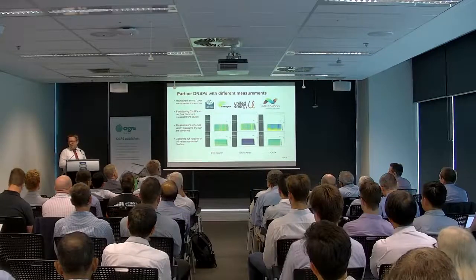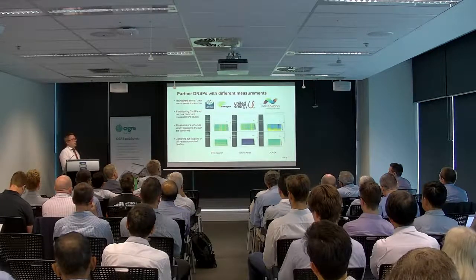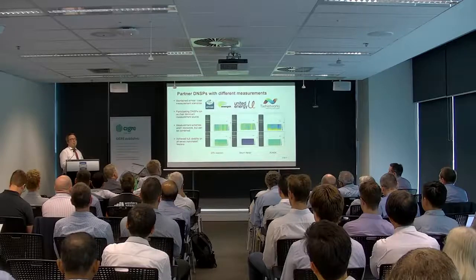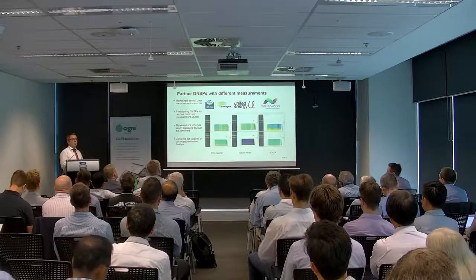The state estimation, once it has run, is as if you had run a power flow simulation. It reveals the most probable system state, and as it is represented, it is complete, so you can calculate each and every operational value. From partial measurements plus the network model plus some load statistics, you get full visibility of the system.